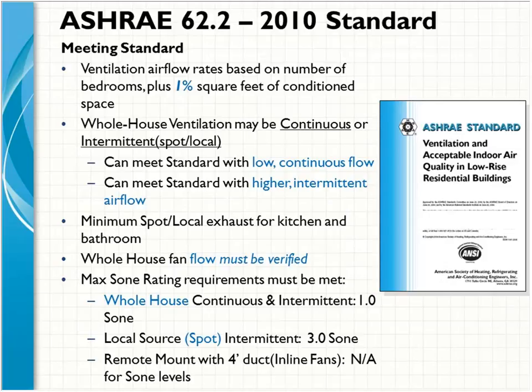So on the ASHRAE 62.2 code, there's going to be a 1% calculation on the square footage for the building. And when we talk about the 2013 version, you're going to see that that number goes up to 3%. And we'll talk about why that is. And there's a couple of different ways, of course, that we can meet the code. We can meet it by running a fan at a low speed continuously. And that's often the preferred method because it's constantly refreshing the air in the home. Or we can run it at a higher CFM on an intermittent basis.